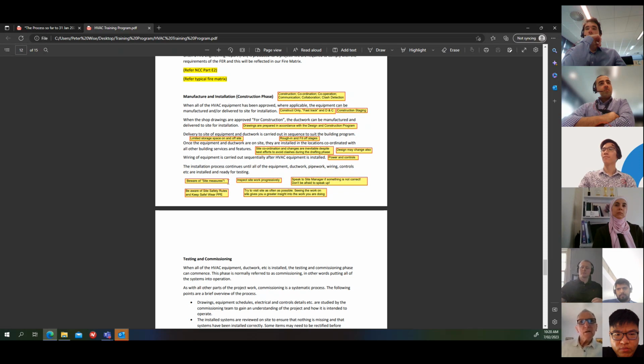So on site, our guys didn't ask the engineering team, they just went ahead and made this transition. Let's say the duct was a metre square - they made a transition down to 500 square to get through this hole and then back out to a metre square. Can you imagine what that does to your fan? That's a nasty restriction and a very high velocity through that point.